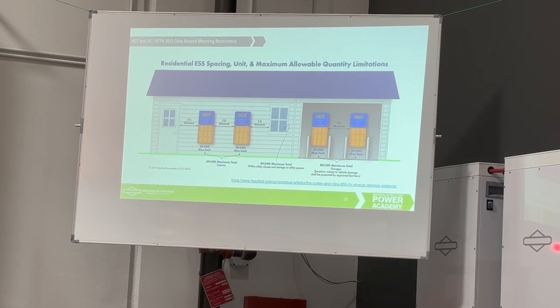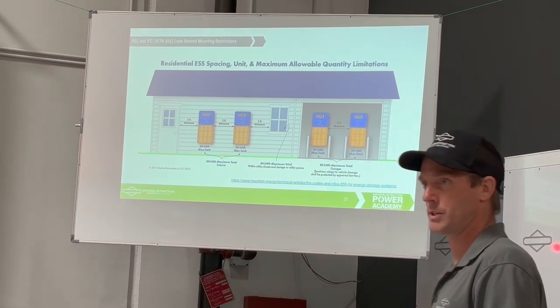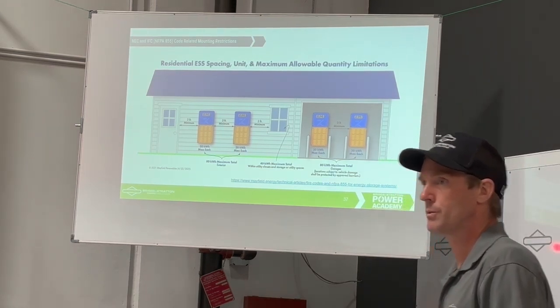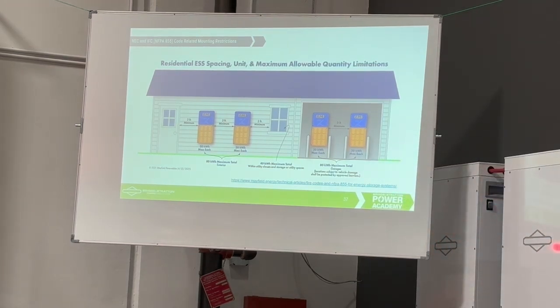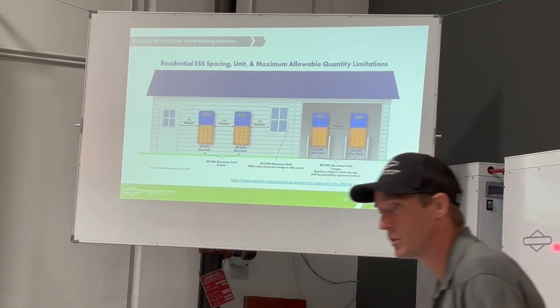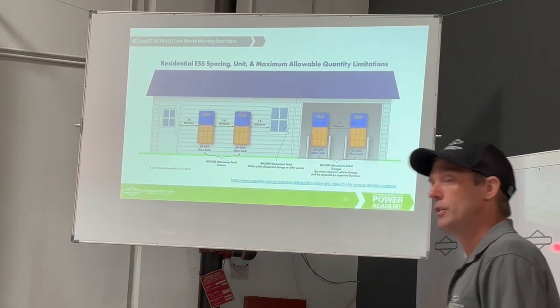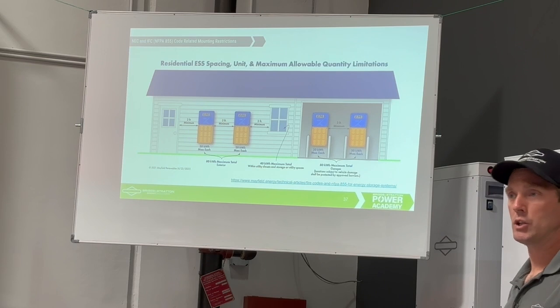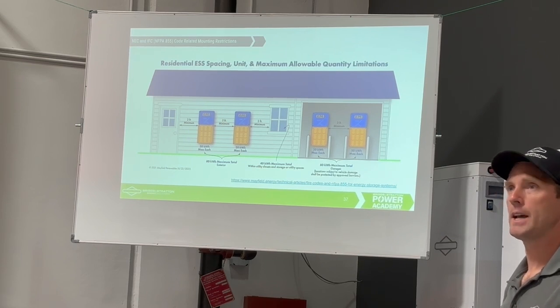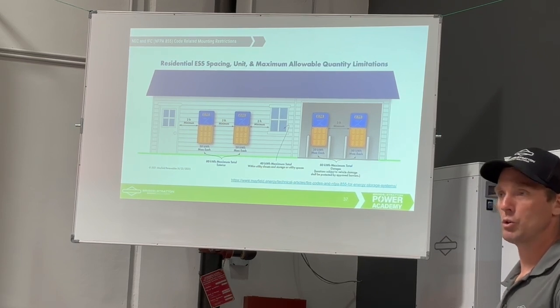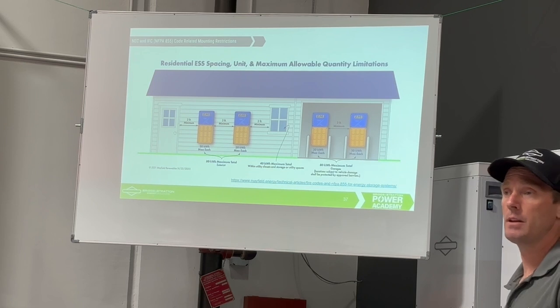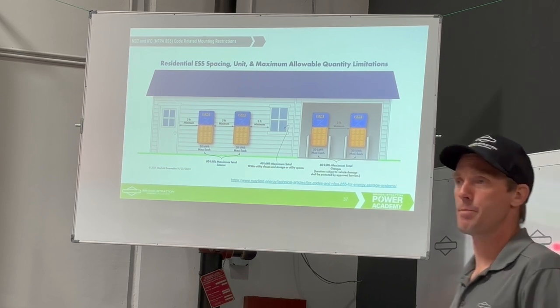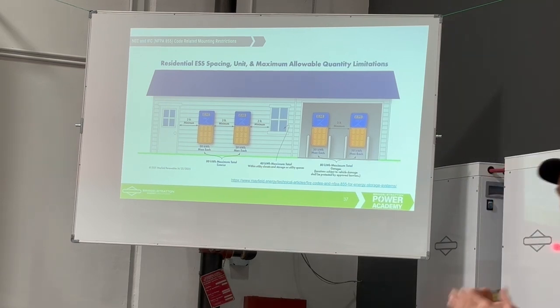36 inches between, from the manufacturer. That's part of NFPA 855. It's 36 inches between. Some manufacturers go down to 6 inches. Those change, and we can do additional testing with UL to get those reduced. We haven't done that yet, but we could get those even tighter. So some manufacturers pay for that extra testing to get their batteries even closer together.